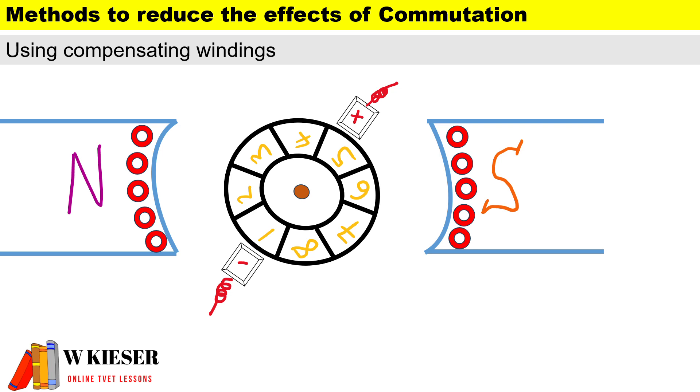Finally, we can use compensating windings, which brings us to our example today. Compensating windings are windings slotted inside the pole shoes, and the current through the compensating windings is connected in series to the armature conductors.